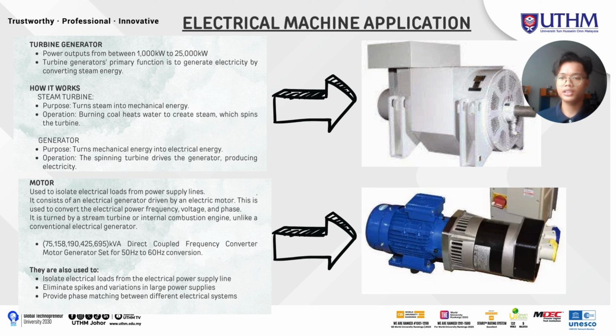There are four components that I put in the electrical machine application. The first one is the turbine generator. The power output is between 1000 kilowatt to 25,000 kilowatt. The turbine generator's primary function is to generate electricity by converting steam energy. The steam turbine turns the steam into mechanical energy. For the operation, burning the coal heats water to create steam, which spins the turbine. And the generator's purpose is to turn the mechanical energy into electrical energy. In operation, the spinning turbine drives the generator, producing electricity.